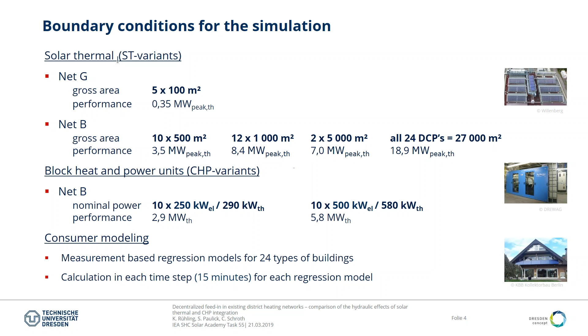Additionally, we had to make a good consumer modeling. These are models based on regression models for 24 types of buildings, and we calculate the real action depending on the supply line temperature of the district heating network. We produce results for the return line temperature of the customer and the 7 variations of the simulation study on the left-hand side.